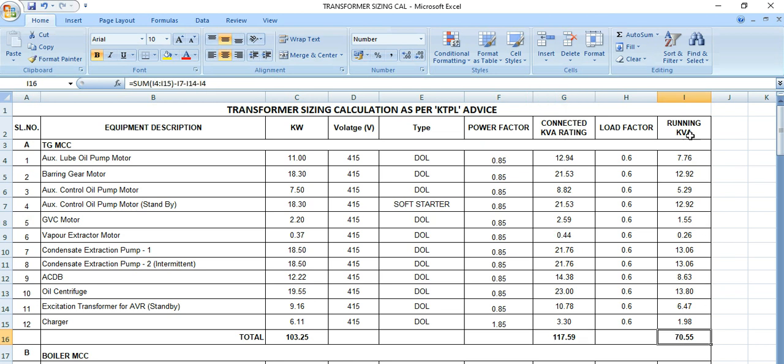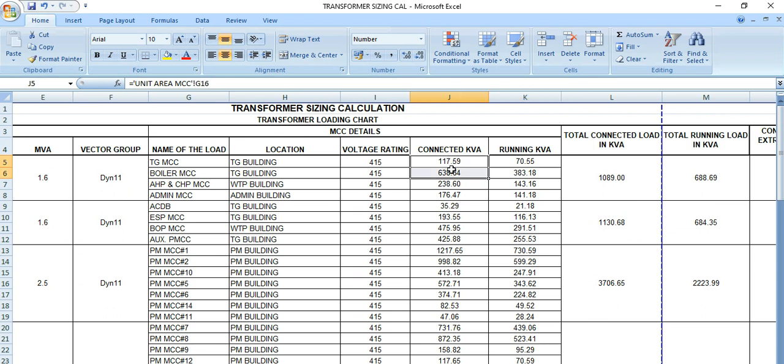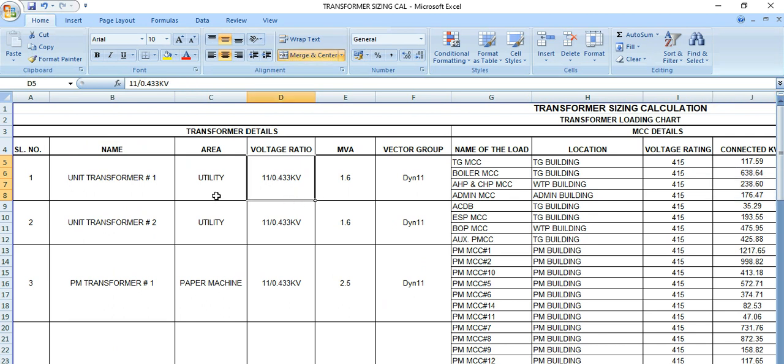And 70.55 kVA is the running kVA. So from here this data is being fed, and all the MCCs, all the areas which are being fed from this particular transformer, those are added here. This is 11 by 0.433 kV utility transformer, unit transformer, and this rating is 1.6 MVA. Vector group is Dyn11.